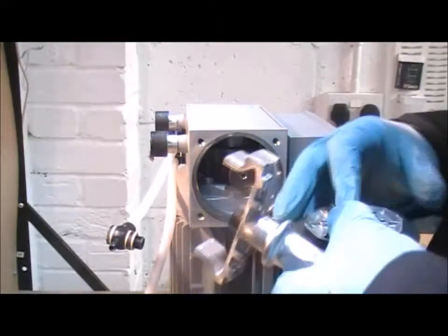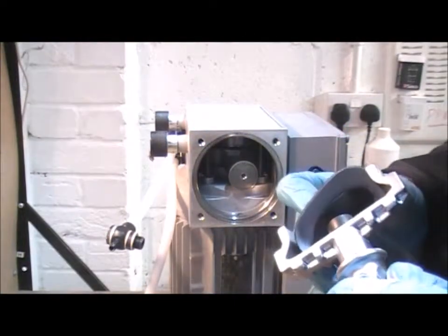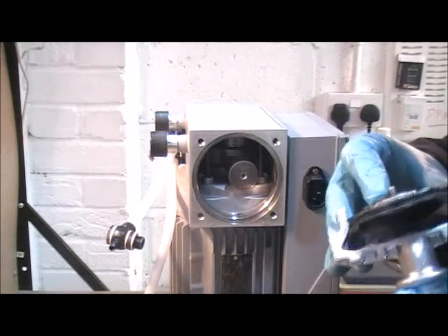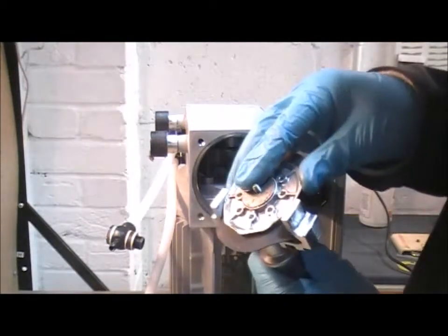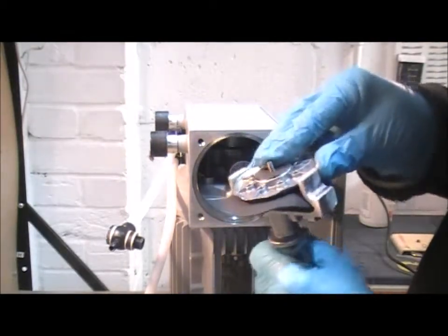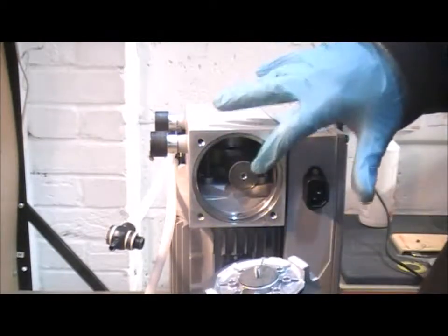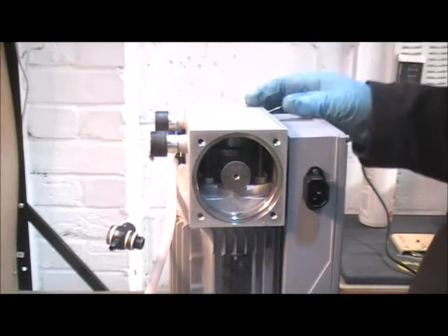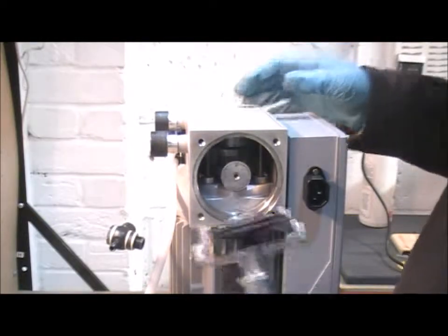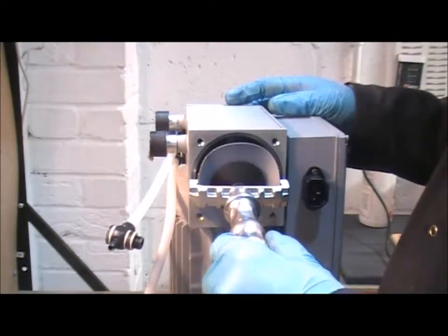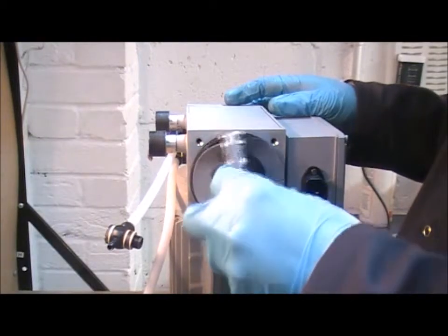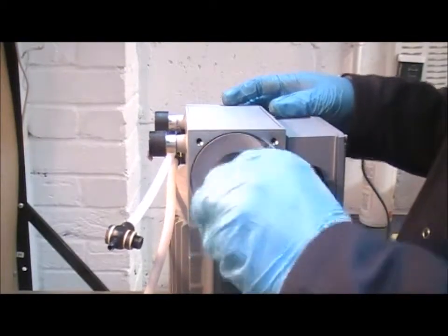And then folding up the sides just as the tool came out, you can locate that. And now at this point this is why it's easier to have the pump in this orientation, because now it's just a case of lifting the tool with the whole assembly up and screwing it into place.